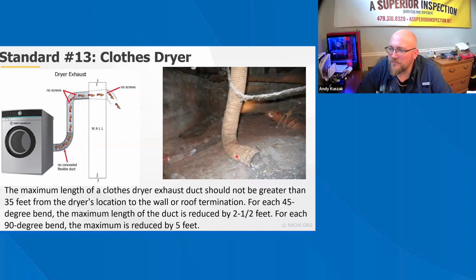The length can be increased only when the make and the model of the dryer is known or when an approved blower fan calculation is provided. The maximum length of the exhaust duct does not include the transition duct. Transition duct means from the dryer to the actual dryer vent that terminates to the outside. Screens are not permitted on clothes dryer exhaust vents because they can trap lint and other debris, which poses a fire hazard. The maximum length of a clothes dryer exhaust duct should not be greater than 35 feet from the dryer's location to the wall or roof termination. For each 45-degree bend, the maximum length of the duct is reduced by 2.5 feet. For each 90-degree bend, the maximum is reduced by, and I think it's 5 feet. All right, so there's a lot to talk about here.